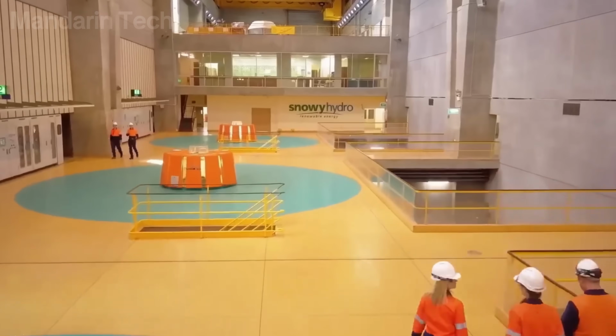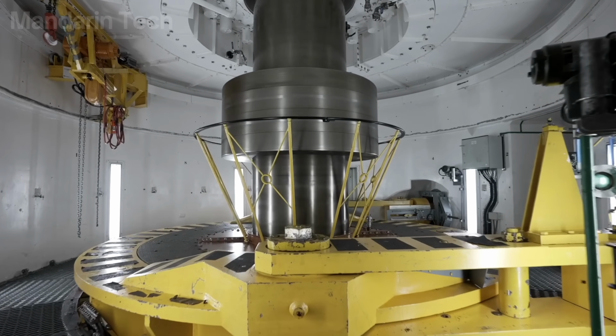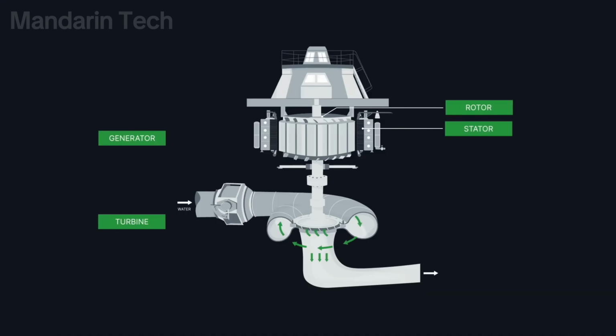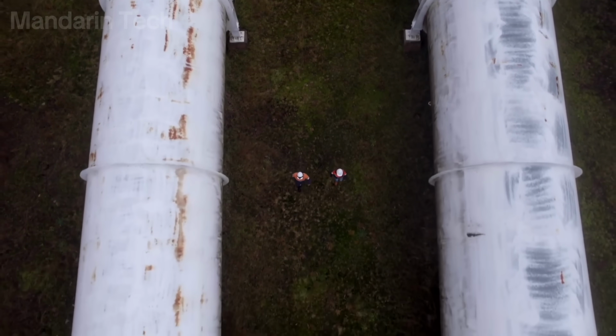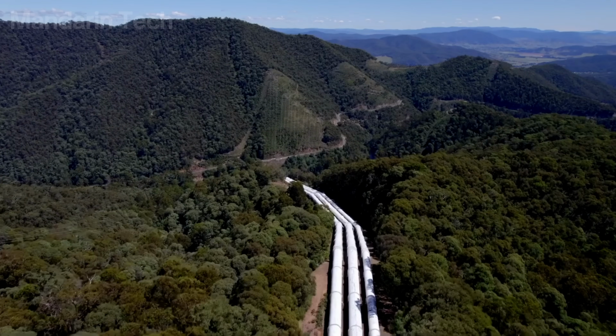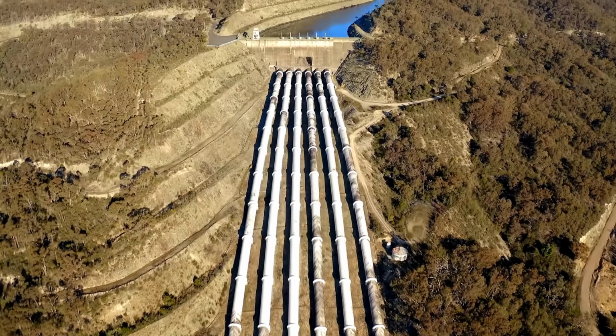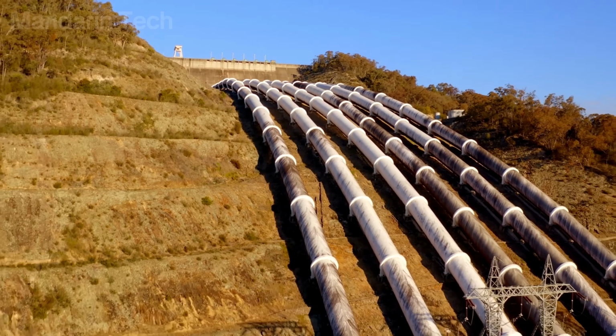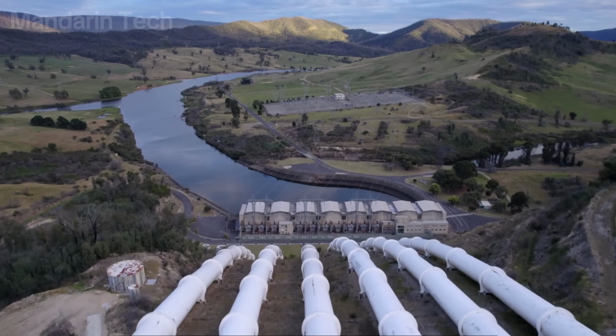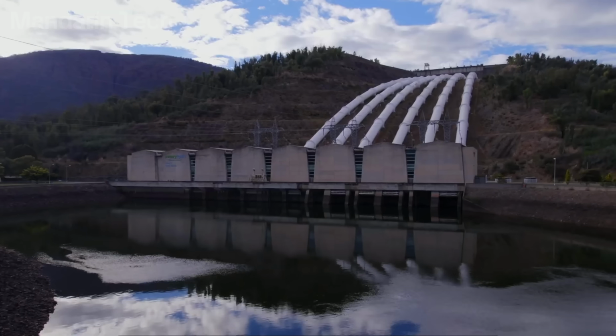From the main tunnel, water will pass through high-pressure steel pipes to the 6 generating units. This section must withstand the full pressure created by the difference in elevation between the two reservoirs. The pipe sections are lowered into inclined tunnels, aligned, welded, and inspected before grout is injected around them, and they are encased in concrete.